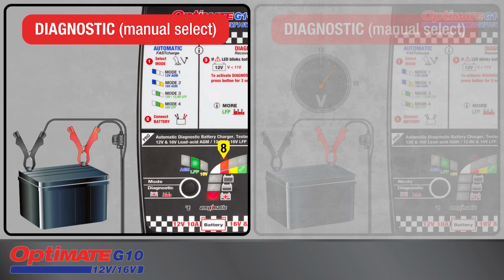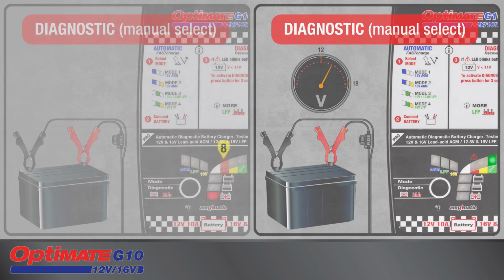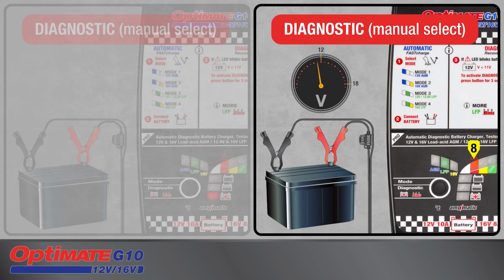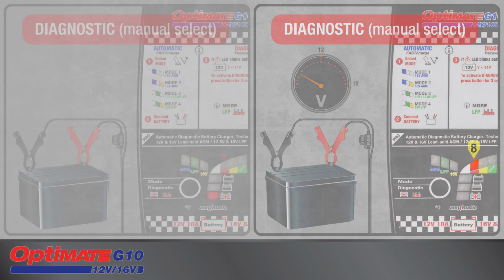Error LED 8 may also blink after LED 3 indicated the recovery mode was active, or if during the battery test the voltage rapidly dropped, indicating a damaged battery. If the indication is as a result of attempting to recover a deep-discharged battery, do not charge again. The battery should be replaced.